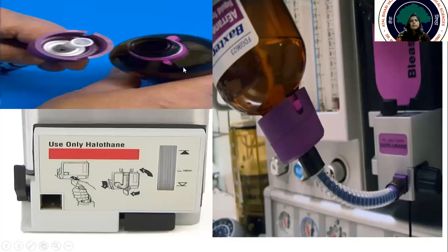To be more clear, this is a bottle. You can see a bottle collar with different ridges of different dimensions, and similar grooves will be seen on the filler tube, which can be fit over the bottle. And here, this is a vaporizer inlet. You just put that filler tube inside here, just like this. To lock it, you have to pull this lever down, and once it is down, raise the bottle upwards, pull this lever, and the vaporizing agent will start flowing inside the vaporizing chamber, and you can see it through the side tube.